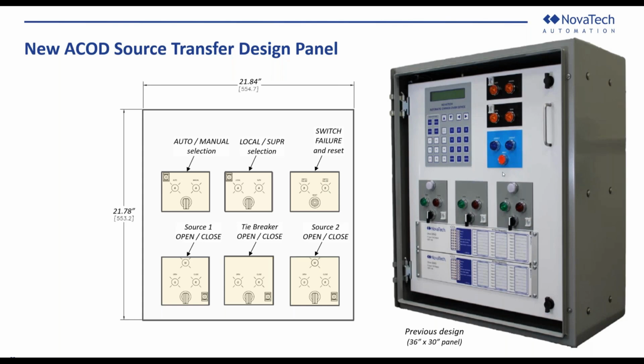A lockout could be caused by a switch failing to operate. That could be due to either a fault on the line or to a mechanical issue with the switch. If a lockout does happen, blue lights are turned on, left for source 1, right for source 2. Then, as I said, ACOD will not close in on a source that's been locked out.